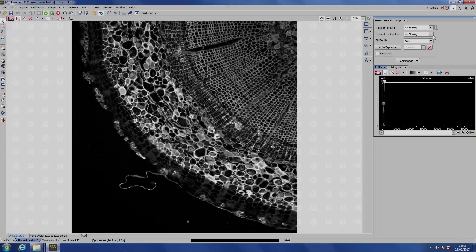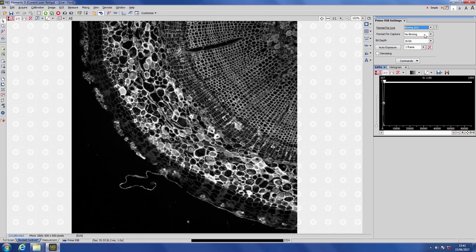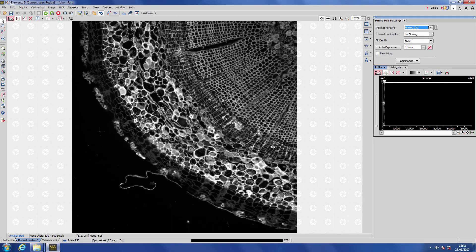If you find that your signals are too weak, you can use binning, meaning you group pixels together. And here we are trading resolution for sensitivity.